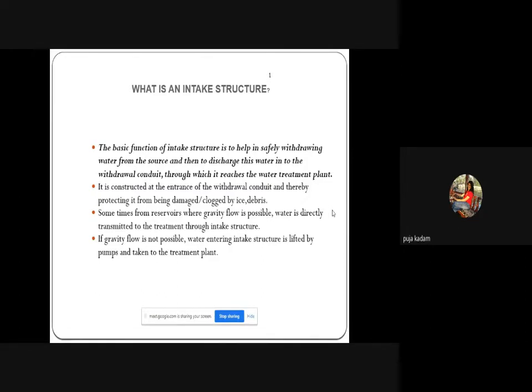If gravity flow is not possible, water entering the intake structure is lifted by pumps and taken to the treatment plant. Depending upon the location of the intake structure — if it is on the upstream or higher side — there is no requirement for a pump room. If the intake structure is on the lower side, a pump room or pump house must be provided to pump the water to the water treatment plant.